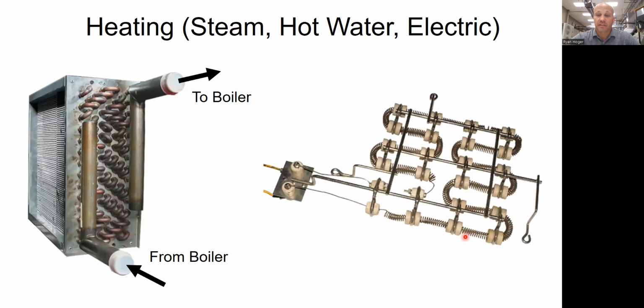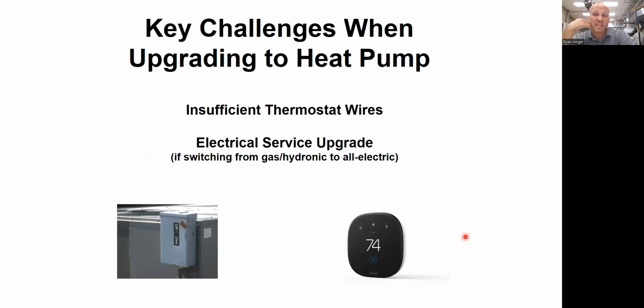Let's say I have electric resistance heating on a split system air handler, meaning one part's inside, one part's outside. There's a pretty good chance I don't have to upgrade the electrical outside. Probably not, right? I already have all the electric I need inside for the electric heater. The outside, the heat pump will probably run on the same gauge wire that I had the AC on. It's probably not going to need this, right?